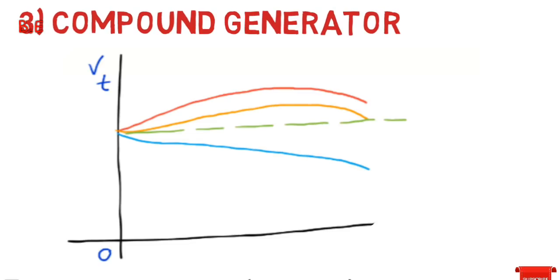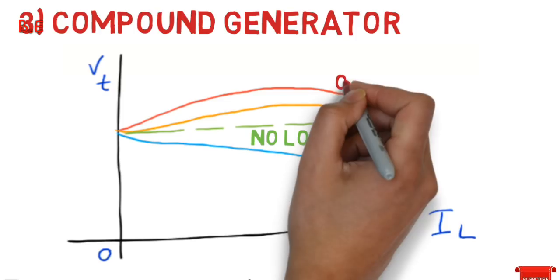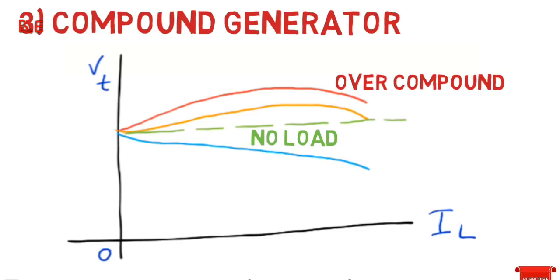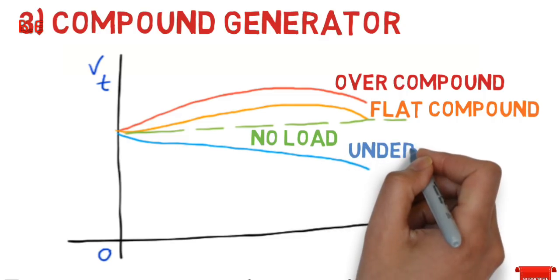Now let's look at the compound generator. The figure shows the characteristics of the compound generator. If the series winding ampere-turns are adjusted so that the terminal voltage remains constant even as current increases, the generator is called a flat compound generator. And if the winding has fewer turns than required for flat compounding, it is called an under-compound generator.